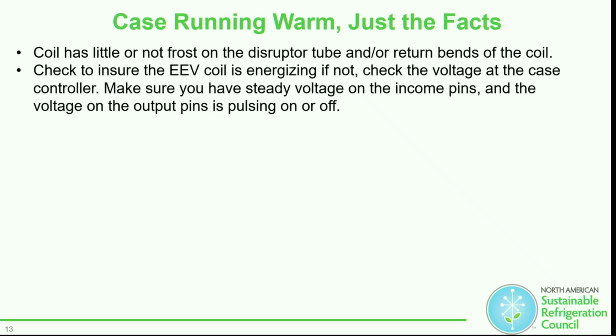Check to ensure the EEV coil is energized. If not, check the voltage at the case controller, making sure that you have a steady voltage on the incoming pins and the voltage on the output pins is pulsing on or off. One of the things that you can check as well, these are typically for the pulsing valves, they are solid state controls. Make sure that when they are closed you have no resistance. Maybe it's putting a little bit of resistance on there, which is not giving the coil the full power that it intends in order to open up that actual plunger.